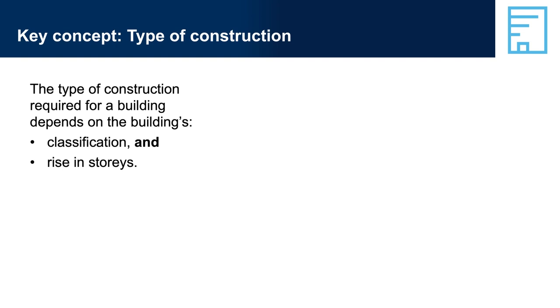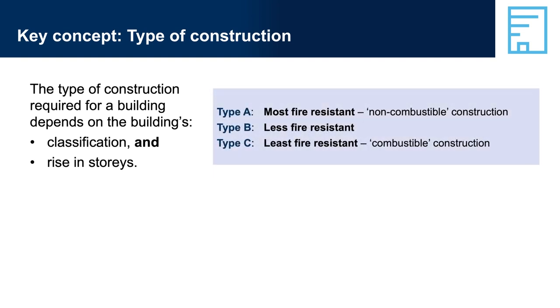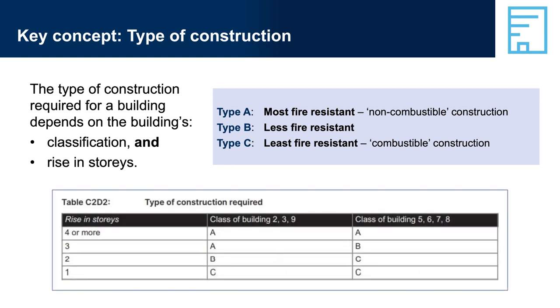The height of the building determines the likely evacuation times and difficulty. Thus, these two factors are used to determine the minimum type of fire-resistant construction required for Class 2 to 9 buildings. The exact requirements for each type of construction are contained in Specification 5 in Volume 1. Some other factors will also determine fire-resistant construction requirements, such as the size of individual fire compartments or atriums in a building. There are special rules for some configurations of some building classifications, such as buildings with multiple classifications.